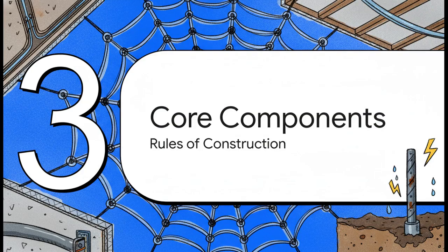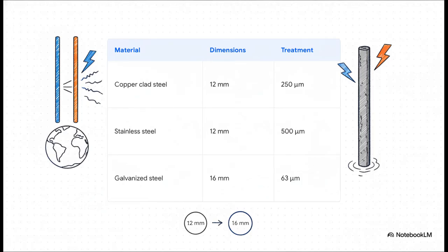Section 3, Core Components and Sizing, the Rules of Construction. Now, obviously, a safety net is only as good as the materials it's made from, right? Which is exactly why the standard dictates some really strict minimums. These components have to survive decades, hidden inside walls, up in ceilings, buried in damp soil, all without corroding or failing when you need them most. Now, what's really interesting about this slide is the dimensional differences in Table 5.2 based on material. A copper-clad or stainless steel rod only needs to be 12 millimeters thick. But if you decide to use hot-dipped galvanized steel, well, the standard requires a thicker 16mm circular rod.